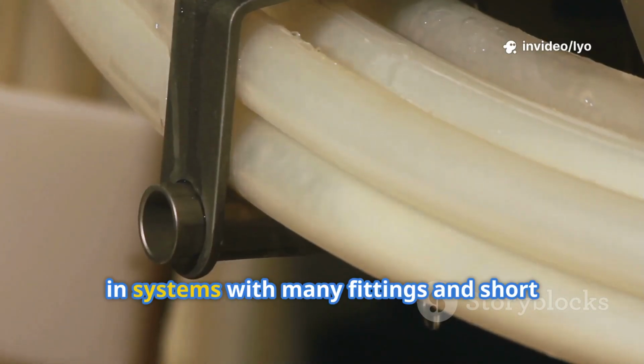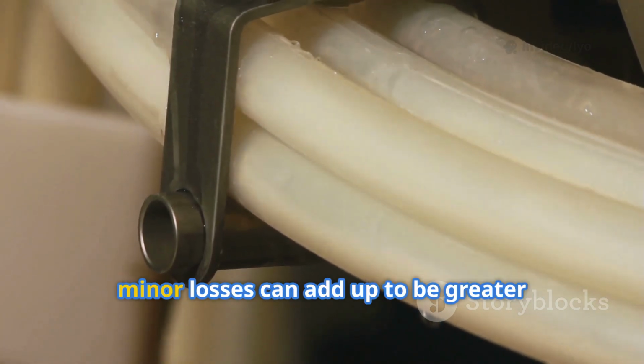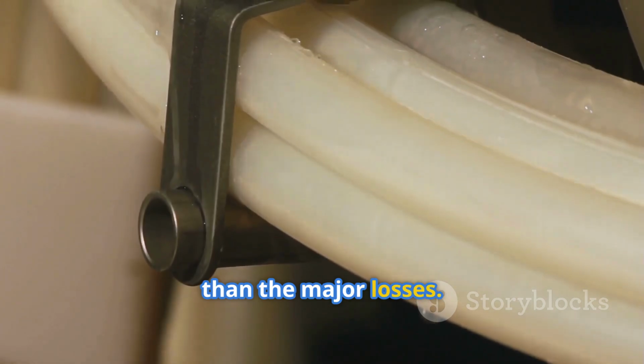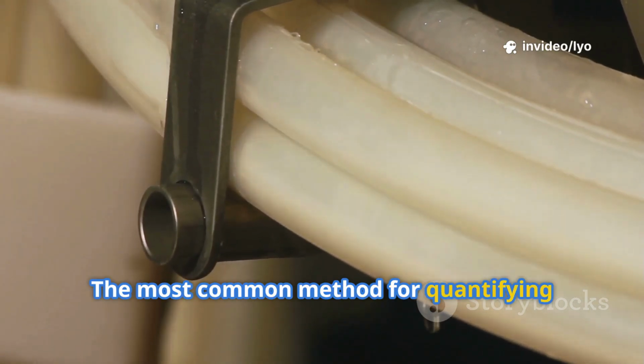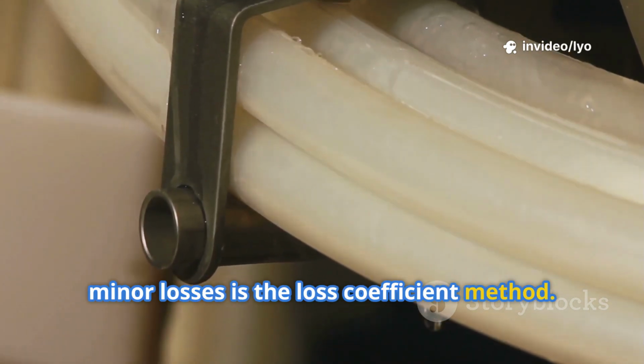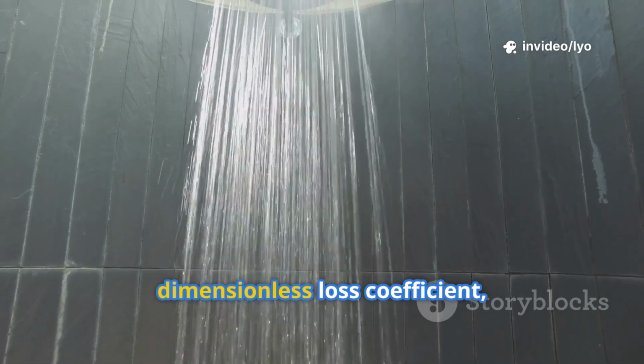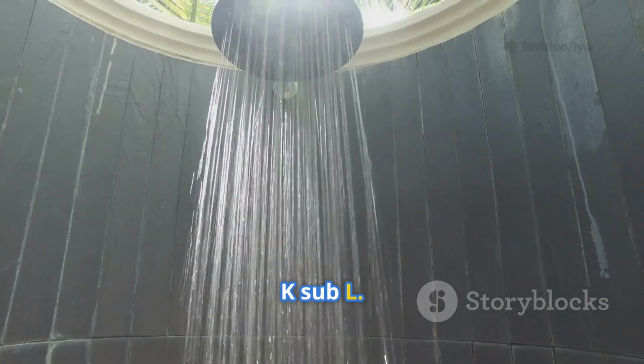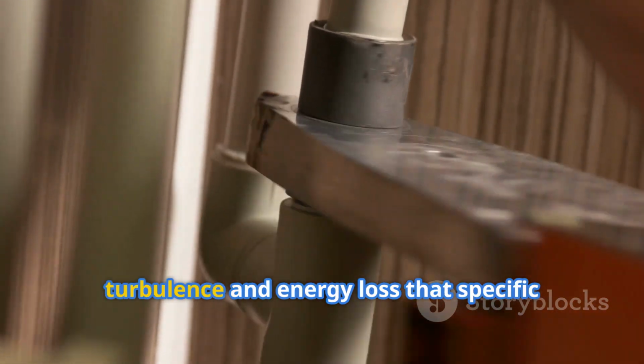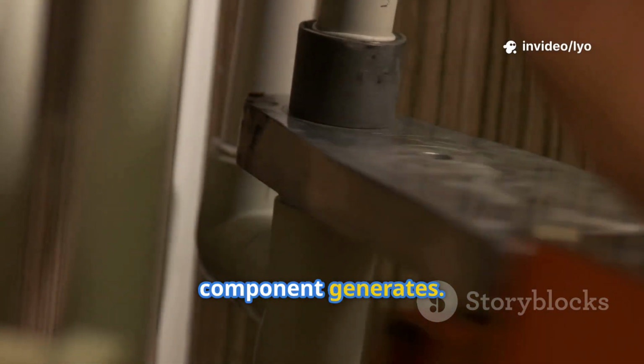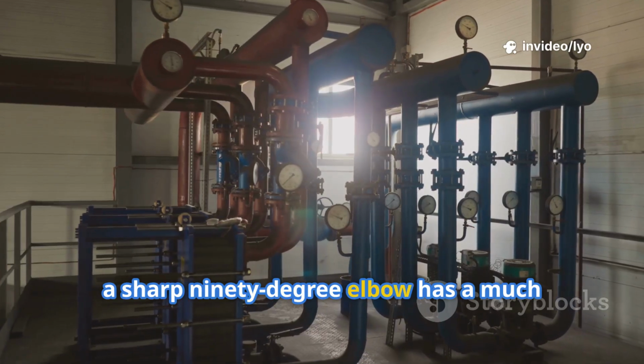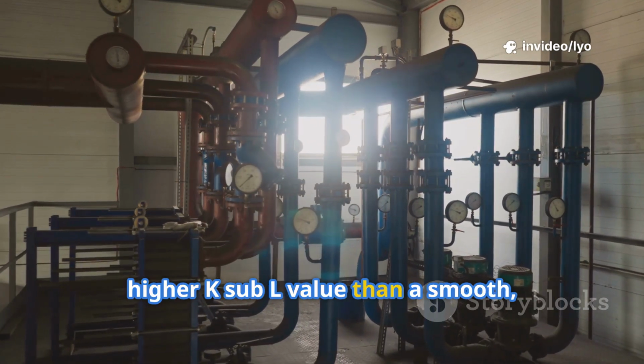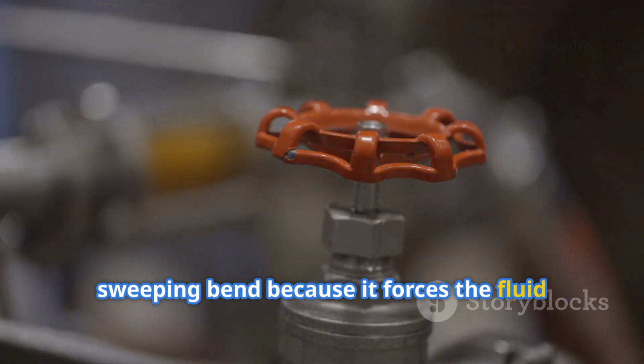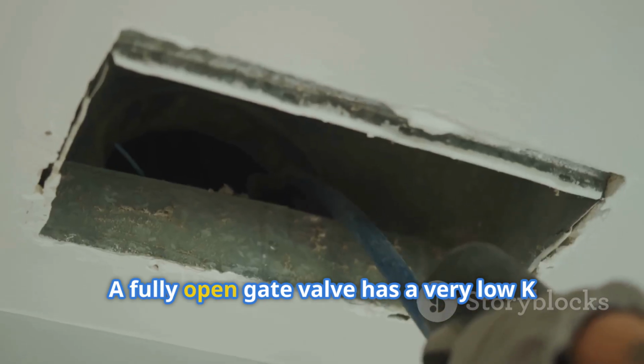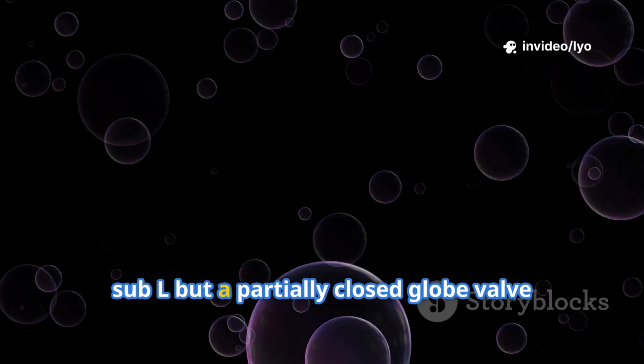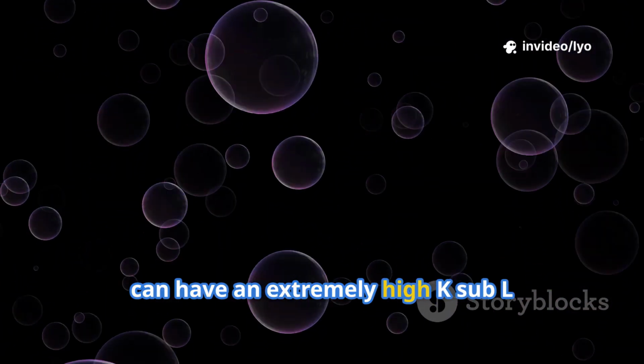Despite their name, in systems with many fittings and short pipe runs, minor losses can add up to be greater than the major losses. The most common method for quantifying minor losses is the loss coefficient method. Each type of fitting is assigned a dimensionless loss coefficient, K sub L. This K value represents how much turbulence and energy loss that specific component generates. For example, a sharp 90-degree elbow has a much higher K sub L value than a smooth sweeping bend because it forces the fluid to make a more abrupt turn. A fully open gate valve has a very low K sub L, but a partially closed globe valve can have an extremely high K sub L.